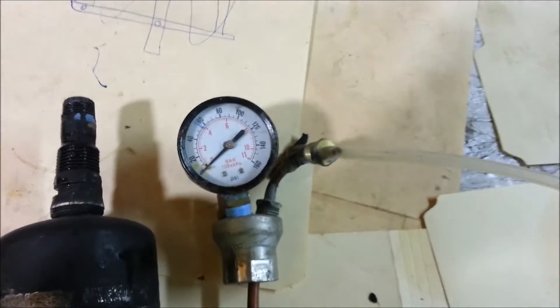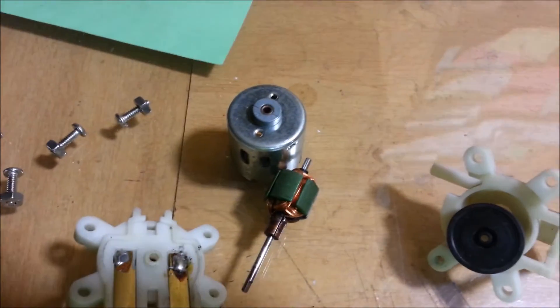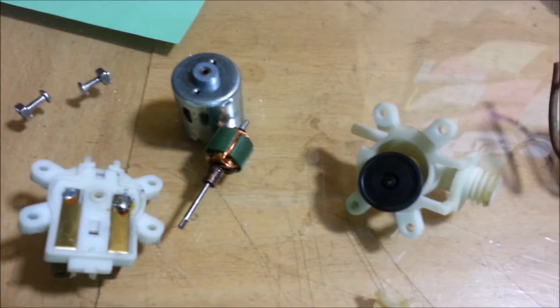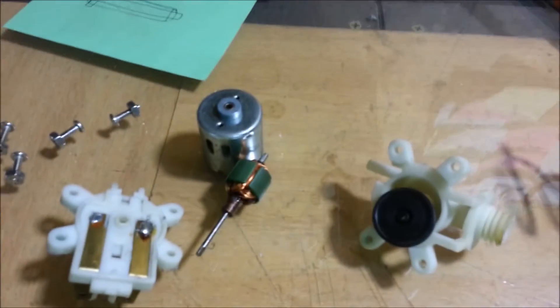I really wish I would have written down some of the operation parameters to get an idea of what type of pressure it takes to push water through a steam coil like this. I'm pretty sure this little pump isn't going to do it. Vapor lock is just going to blast water right back through it, maybe even steam.